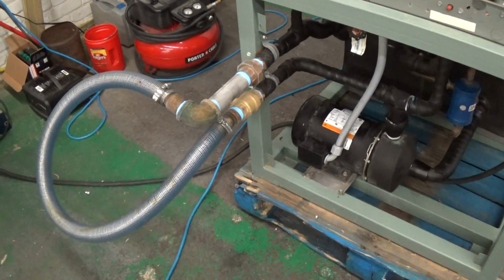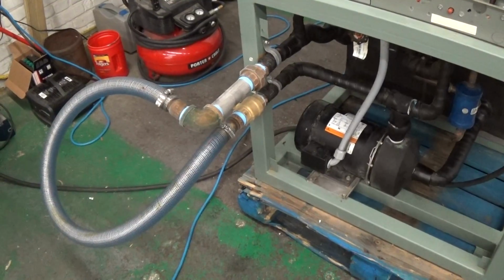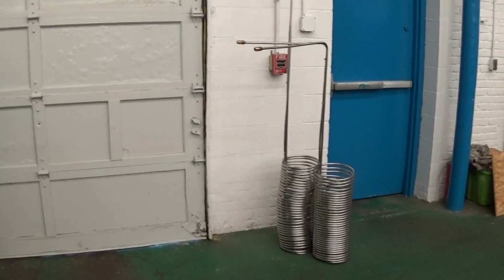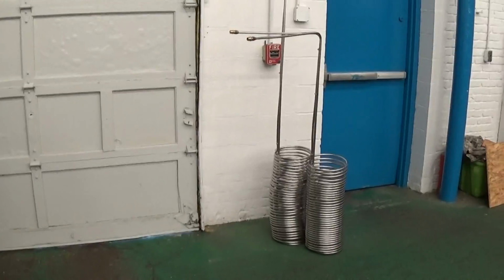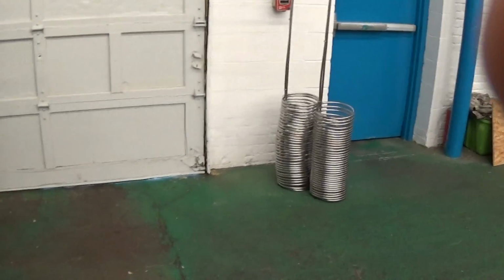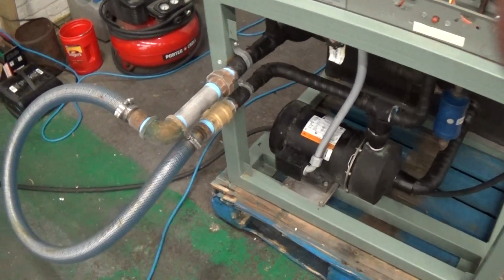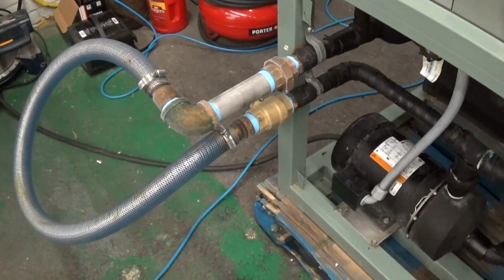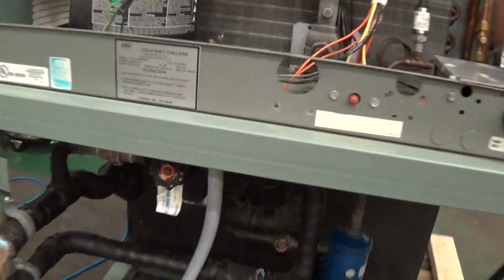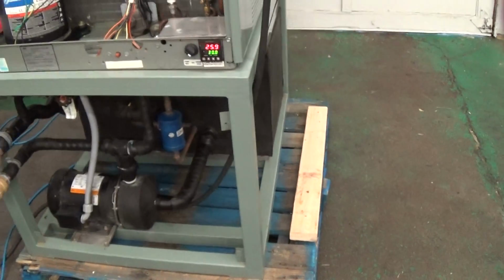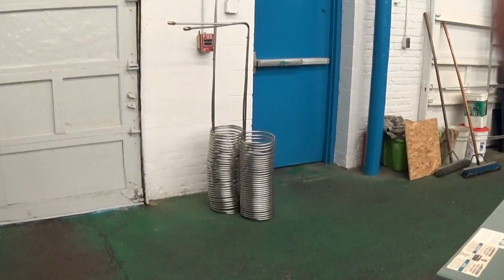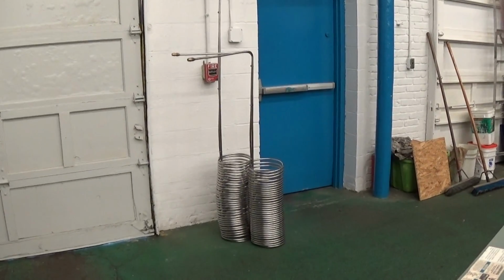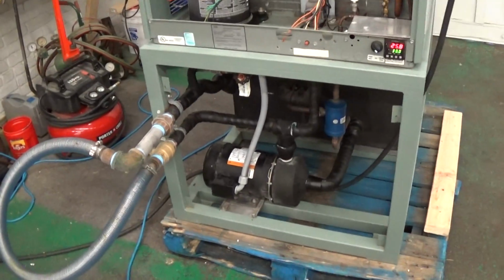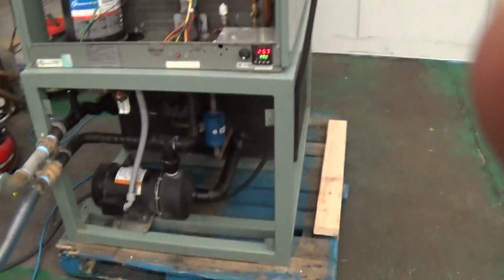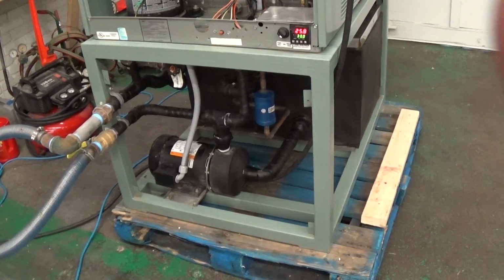Might be a good idea to put a pressure gauge or 2 before the inlet and the outlet of the heat exchangers here, just to record, monitor and compare over time what gives you the best heat transfer, because you'll be able to adjust the amount of flow going into those exchangers by your shutoffs here, combined with your bypass there. By tweaking those and measuring how quickly you're bringing down your tank with those 2 immersion coils, and that's 200 feet of 1/2-inch stainless steel, that may help you dial in your process. So we're going to put the covers back on and get this baby ready to ship and post this video.